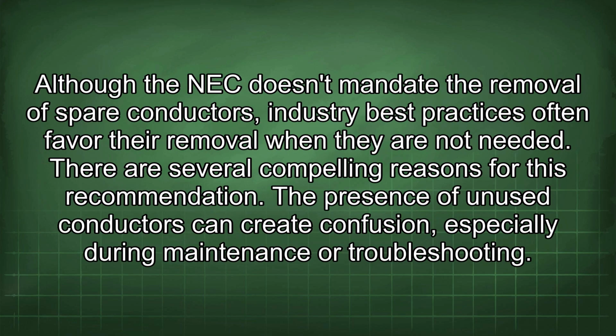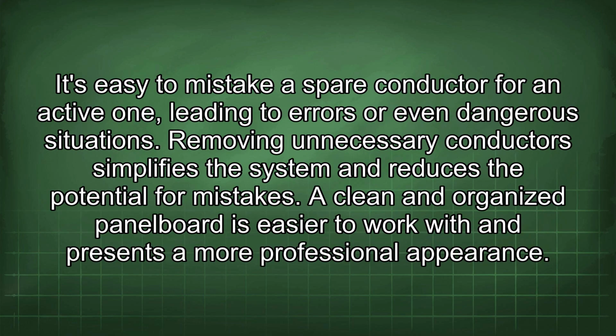Although the NEC doesn't mandate the removal of spare conductors, industry best practices often favor their removal when they are not needed. There are several compelling reasons for this recommendation. The presence of unused conductors can create confusion, especially during maintenance or troubleshooting. It's easy to mistake a spare conductor for an active one, leading to errors or even dangerous situations. Removing unnecessary conductors simplifies the system and reduces the potential for mistakes.